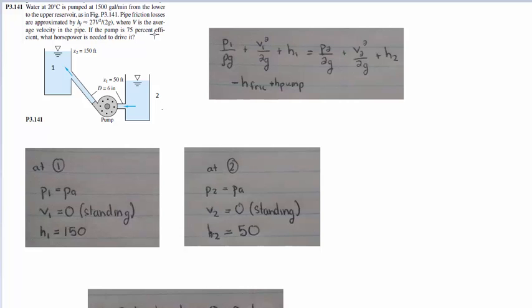We write out our power as ρQg times H_pump and substitute everything in. The 0.75 comes from the pump efficiency. If your pump is only 75% efficient, you need more energy than you calculated. Multiplying by a number smaller than one gives you less, so you divide by 0.75 to get the actual power required. That way, when multiplied by 75%, you get what's actually delivered in the system.